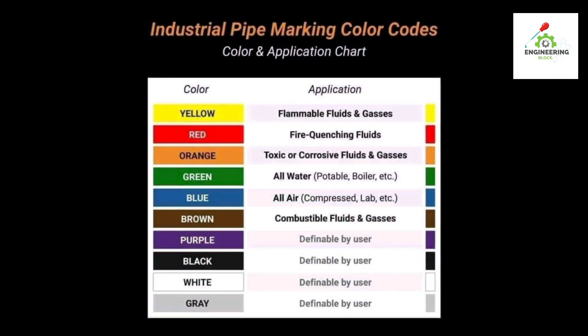Welcome. We will discuss industrial pipe marking color codes, their applications, and where these colors are used. First, yellow color is used for flammable fluids and gases. Red color is used for fire quenching fluids. Orange color is used for toxic or corrosive fluids and gases.